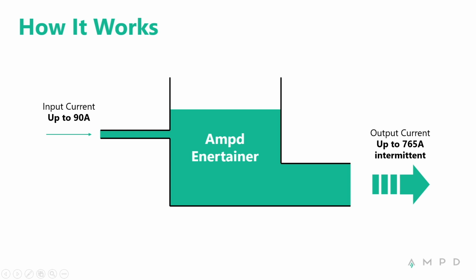So what we do with our battery is you can take a much smaller connection to continually fill up the battery, and then the battery handles those very large power needs on the output. The trick is to make sure the battery never runs out of energy. I talk about this like a water tank: you have a small inbound pipe constantly trickle feeding a tank, and a large pipe on the output which only sends out water or power when it's needed. That has worked very well.